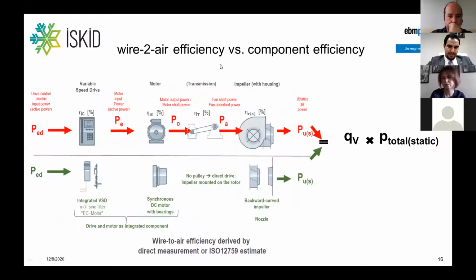So, wire-to-air efficiency versus component efficiency. Wire-to-air efficiency means that the overall fan is tested, including all the necessary components such as the drive, the motor, the transmission if there is one, and the fan itself. This ends in the air performance, which is the product of flow and pressure, again total or static. In the standard ISO 12759, it's mentioned that the most reliable way to express wire-to-air efficiency is by direct measurement, because there the accuracy is highest.